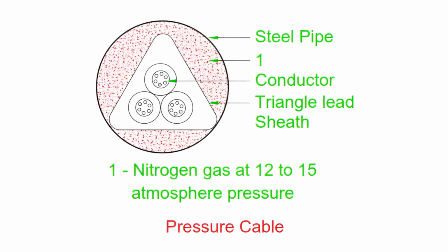Gas pressure cables are even more interesting. They use dry nitrogen gas at high pressure inside a pipe to compress insulation and eliminate air pockets. This makes the cables safer and capable of carrying more load at high voltage levels.